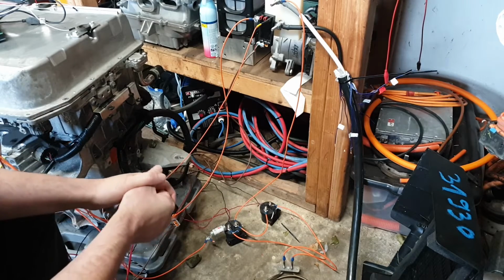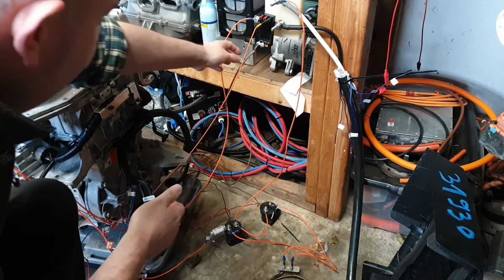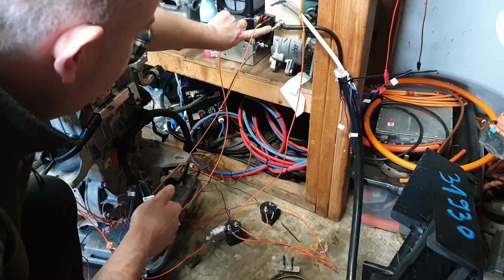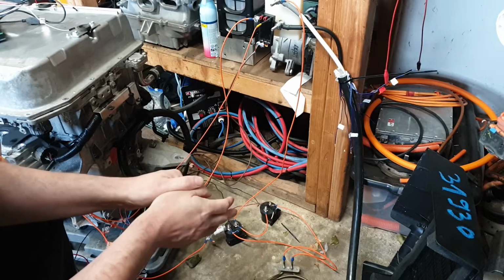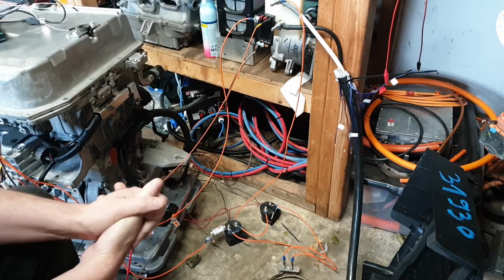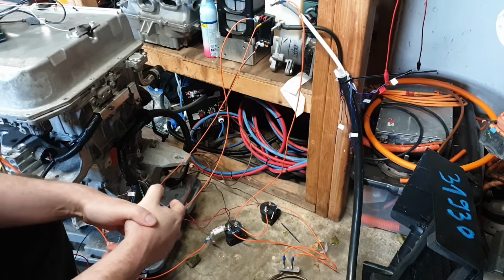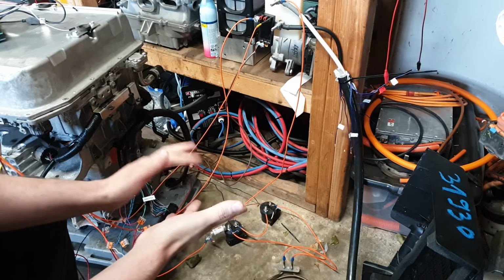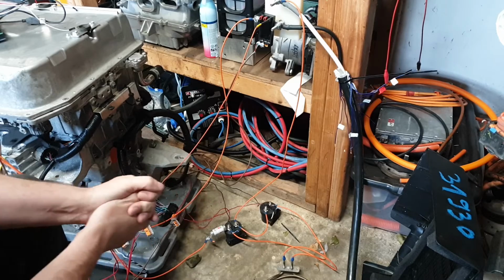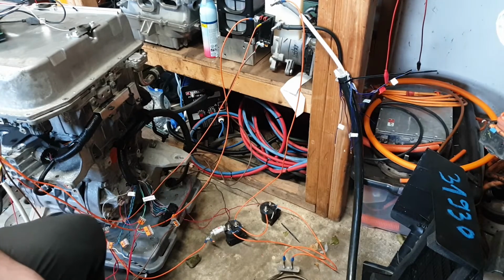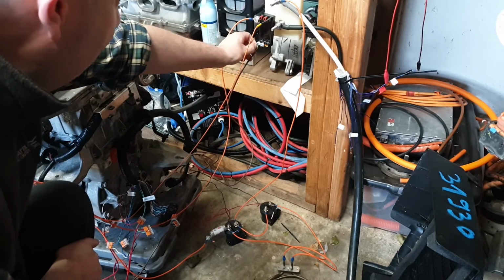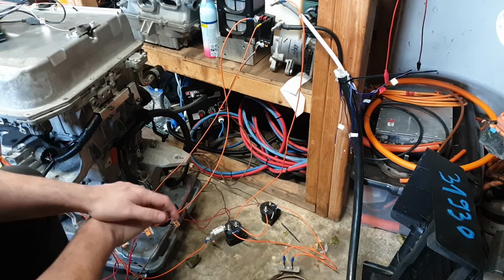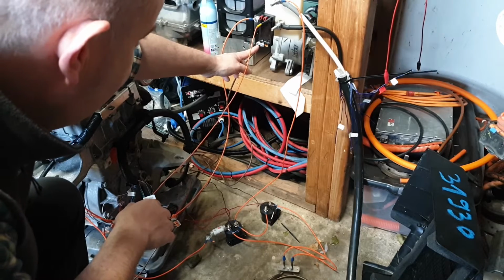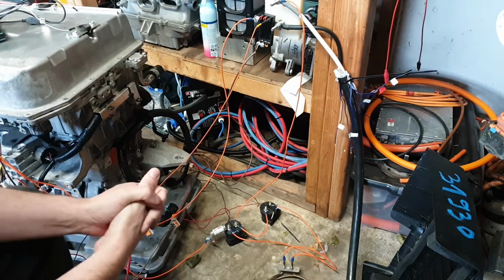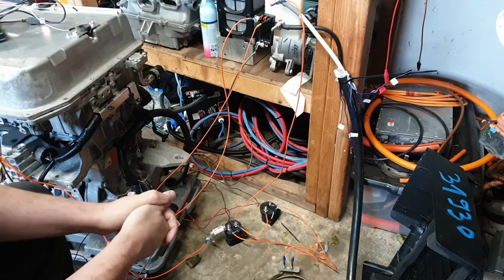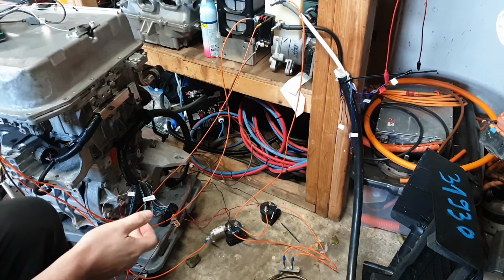One thing I will note is we have a little 4-core wire here going into our ISA shunt. Just to remind folks, the ISA shunt is our battery monitoring system, and it informs the VCU about voltage, current, temperature, amp hours, kilowatt hours, and all that good stuff, via CAN. We have a red and black wire, which is a permanent 12-volt supply, and a green and yellow wire, which is our CAN high and CAN low. We connect those to the relevant CAN external 2 low and CAN external 2 high pins of our VCU.